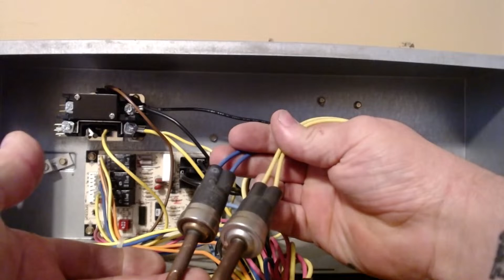Here's your outdoor fan. So right here, this wire, OF1, OF2, 11, 23, 23, 21. Single pole contactor. Off to our capacitor. High pressure switch. Low pressure switch. Now, there have been numerous videos that you would see leaks here, the tops of these, or actually at the wire. I haven't run across one, but I've seen the videos.